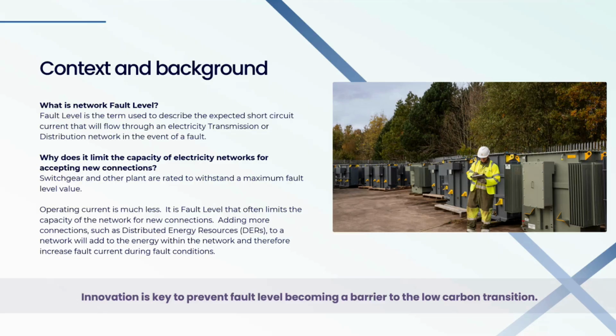To give an example of a fault that we could experience, imagine a tree falling onto an overhead line conductor. That tree will create a low impedance path between the high voltage conductor and ground, and all the energy that's within the network at that point in time will rush towards that fault location, and that is the fault current flowing through the network. What happens next is our network protection devices will see that fault current, and they will signal the relevant circuit breakers to open to de-energize that circuit and make the circuit safe.